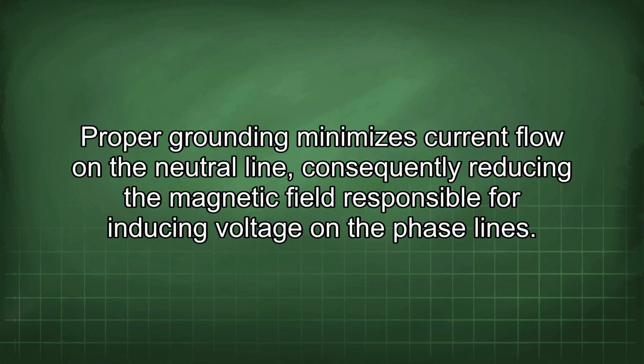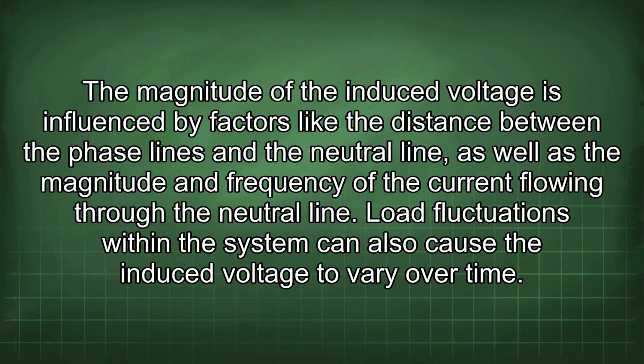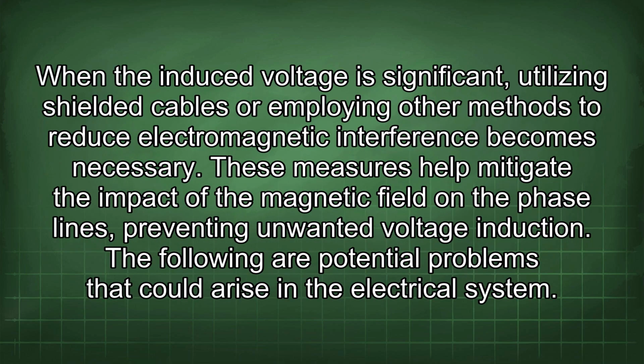Proper grounding minimizes current flow on the neutral line, consequently reducing the magnetic field responsible for inducing voltage on the phase lines. The magnitude of the induced voltage is influenced by factors like the distance between the phase lines and the neutral line, as well as the magnitude and frequency of the current flowing through the neutral line. Load fluctuations within the system can also cause the induced voltage to vary over time. When the induced voltage is significant, utilizing shielded cables or employing other methods to reduce electromagnetic interference becomes necessary. These measures help mitigate the impact of the magnetic field on the phase lines, preventing unwanted voltage induction.